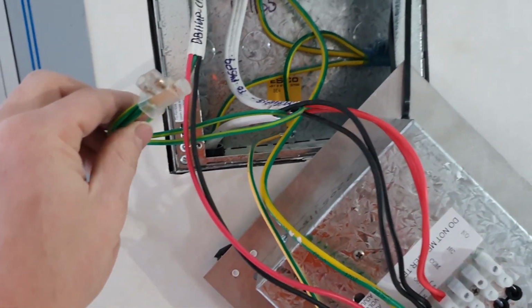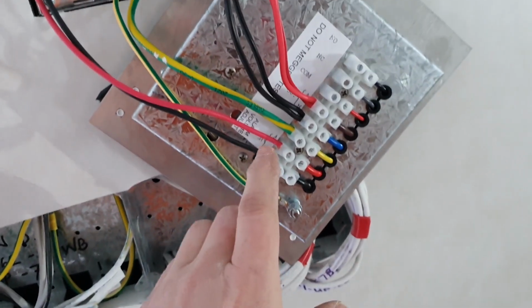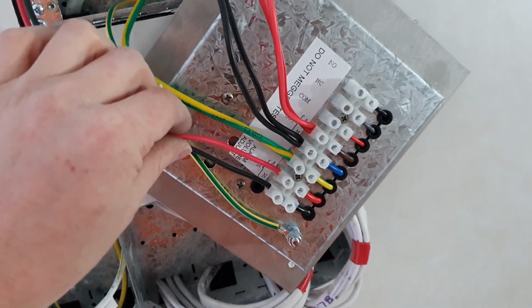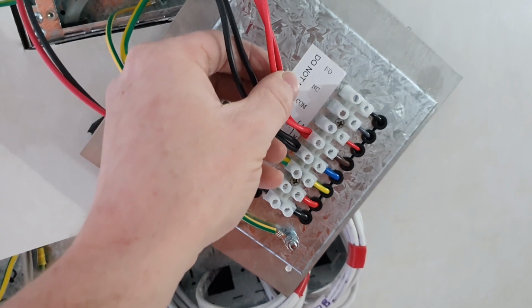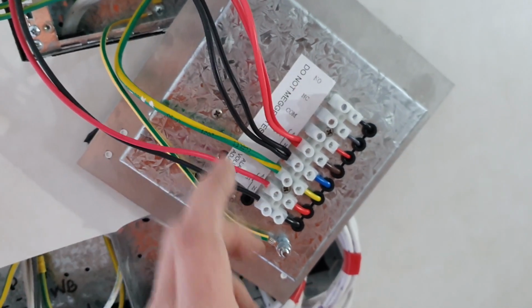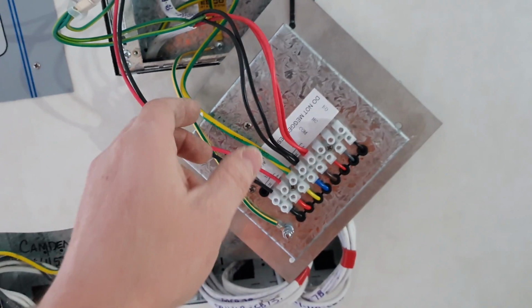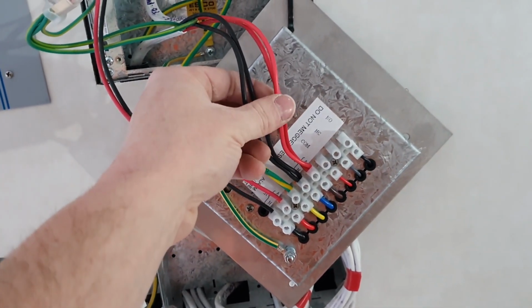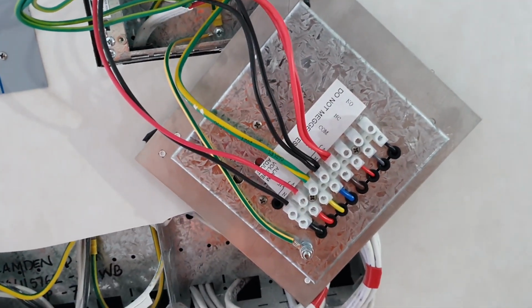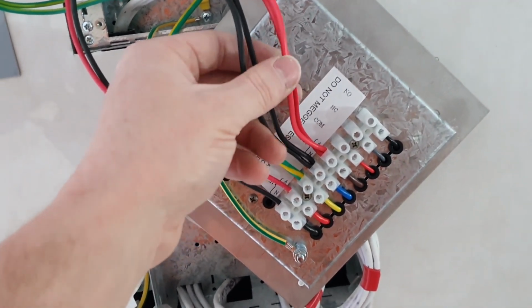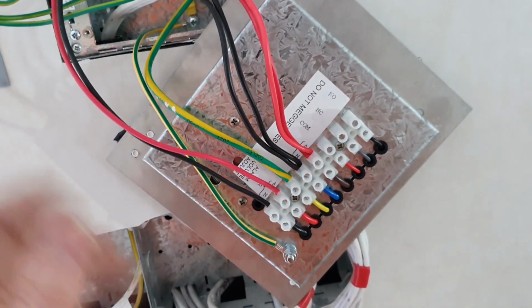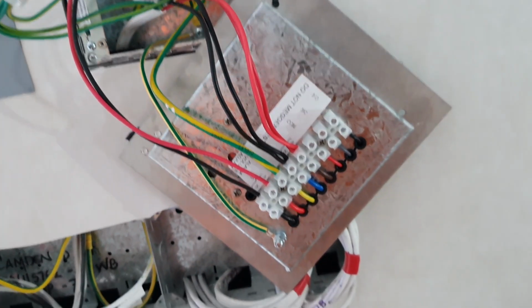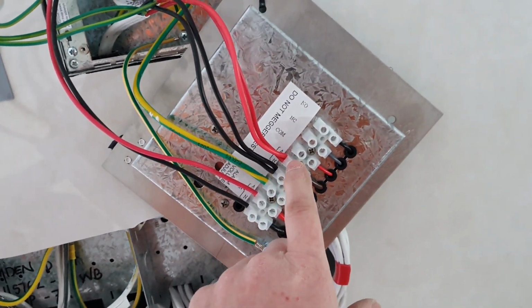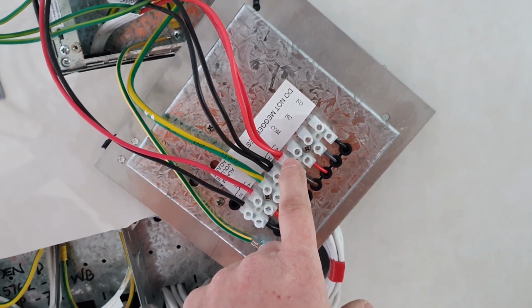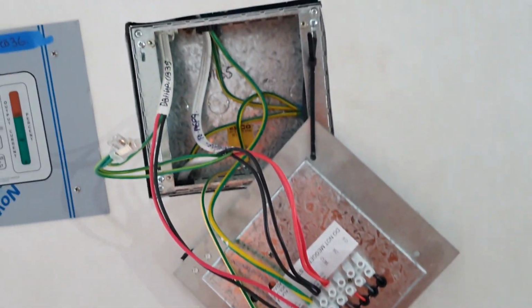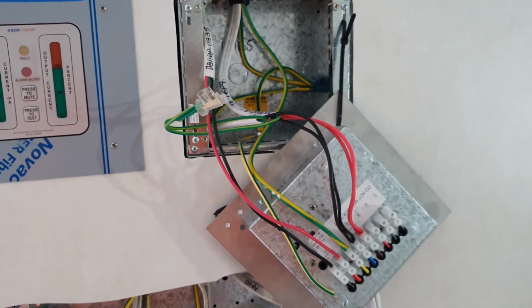So that's it, just a little run through on it. Obviously we've got our active and neutral in, but because this is a line isolation transformer protected circuit, we actually don't have an earth connected to the rest of the circuit. There's a protective earth, but it actually won't trip - it's very confusing, but I'll touch an active cable off one of these transformers and you won't get a belt. I'll do a video on this later, at some stage I think.